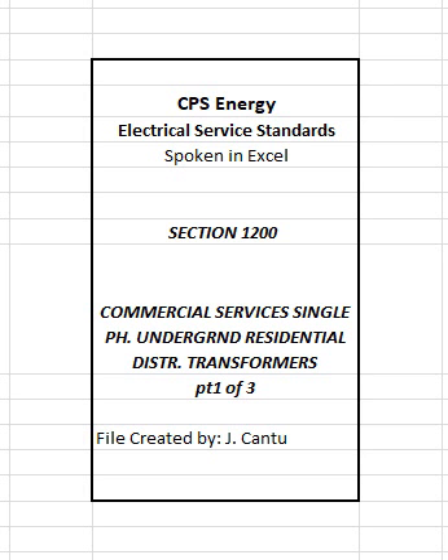Customer-owned service conductors are not permitted to cross property lines even when properties are owned by the same customer. B. Existing transformer. Where a commercial service installation is needed from an existing transformer, the customer will be required to install a tap box in accordance with Article 1205 and Figure 1201, B. Note 1. CPS Energy permits only one commercial service installation from a transformer secondary. Where additional services are required, then a tap box will be installed in accordance with Article 1205.